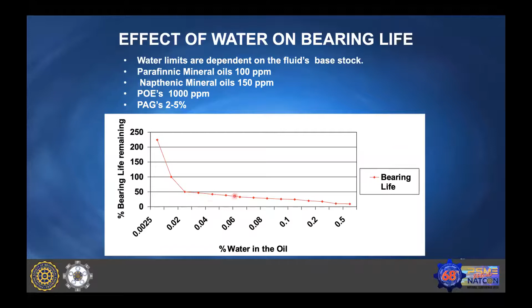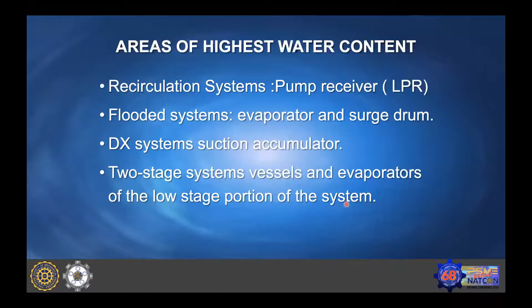Where does this water accumulate? Normally, water accumulates on the low pressure side. Water never accumulates on the high pressure side. If it is a flooded system or a gravity fed system, it will be on the evaporator and surge drum sides. In a DX system, it will be in the suction accumulators. In two-stage systems, it will be on the low pressure side. If it is an ammonia pump system or overfeed system, it will happen in the pump receivers. Why does it happen like that?